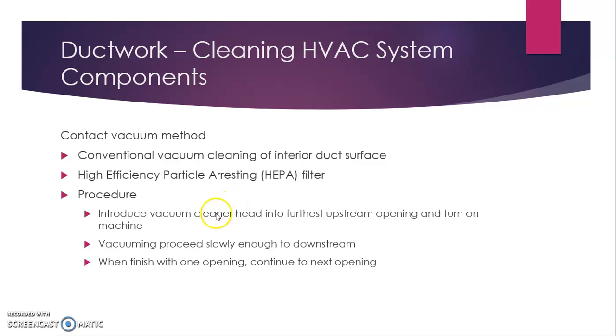The contact vacuum method, which we can call the conventional vacuum cleaning method, is typically and widely used for the cleaning of HVAC systems. We can vacuum the ducting interior and the duct surface, and it will also affect the high efficiency particulate arresting, which is the filter. So we can also vacuum at the filter. The procedure is, first, we introduce the vacuum cleaner head into the furthest upstream by opening and turning on the machine. So we go to the furthest point in the ductwork system first, before coming to the nearest location.